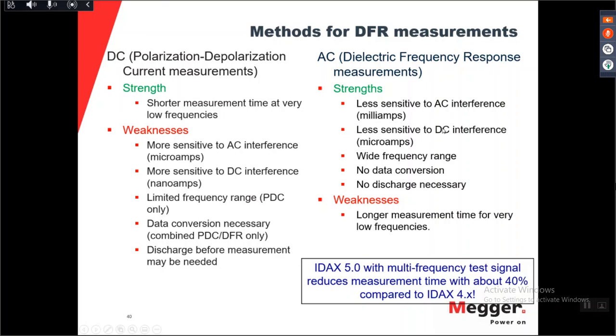So with that, I would prefer to do the DFR or the FDS measurement over the polarization depolarization current, because of the inaccuracies from the different interference currents when you're in the field. If you're in the factory, I would say either method is actually quite well, as the interference currents are so small inside the factory.